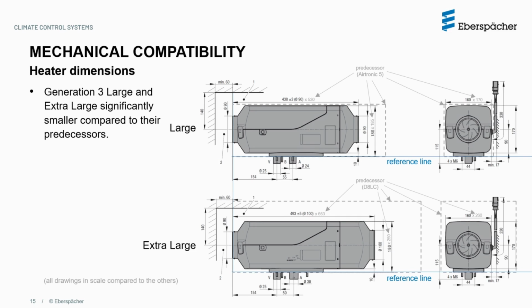When you look at the large and extra large heaters, they are smaller compared to their predecessors Airtronic 5 and the D8LC, which you can see the main dimensions for comparison in the dashed gray lines. For the large size, the inlet duct diameter is 90 mm and the outlet hood diameter is 90 as well. For the extra large size, the inlet duct diameter is also 90, but the outlet hood diameter is 100 mm. Here again we can see that height and width wise, the large and extra large are the same, use the same top and bottom shells, with one of the main differences being the length of the heat exchangers and outlet hoods.